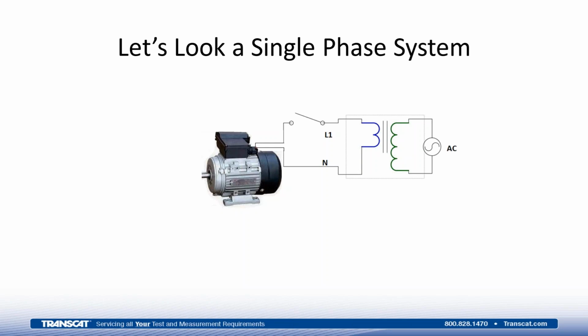that's here. In order to properly monitor this motor, I would put one lead onto the L1 conductor downstream of the switch. I would put another lead of the instrument onto the neutral. As you might remember, I said we would need two conductors to monitor a single-phase load. Those two would be used to measure the voltage being applied to the motor.